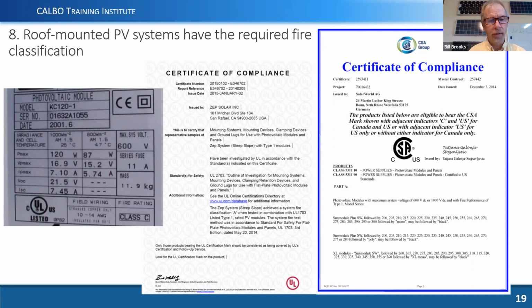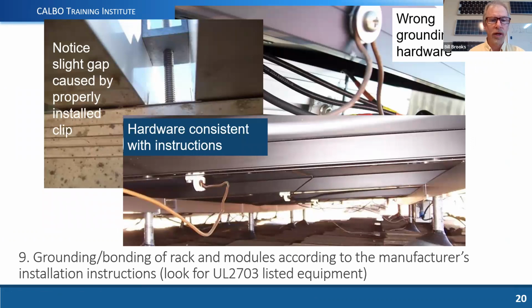So roof-mounted PV systems can have a fire rating, and many of the systems that are sold in California are required to have Class A fire classifications as a system. There are many products on the market, and it's just showing a couple of them here where they have Class A fire ratings on the system. And that would apply to many different communities throughout California, any wildland urban interface areas in California. So if you are in a community and you're not sure whether or not they require Class A for their residential roofing, you can contact them and determine if the address that you're working in requires that.